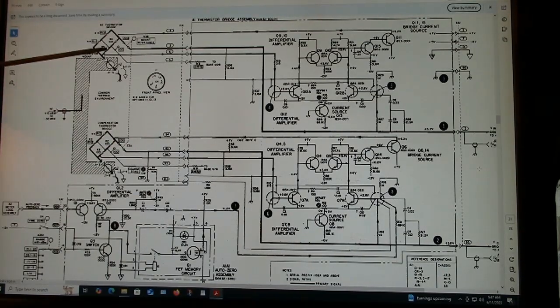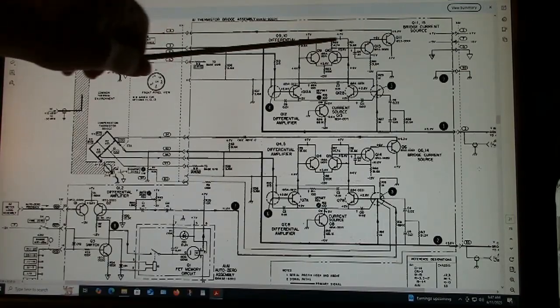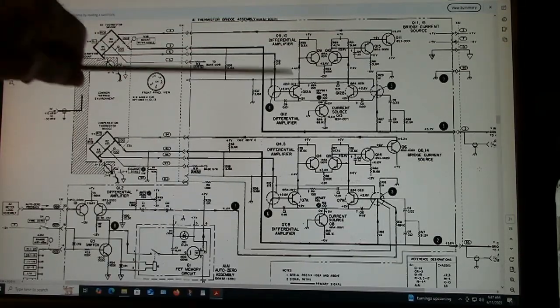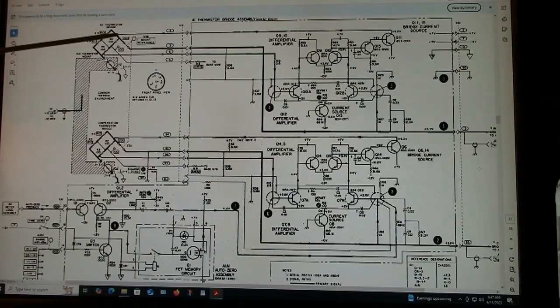Now when you apply RF, that will tend to unbalance the bridge, because this thermistor is heating up, its resistance will decrease. So to maintain the balance, this feedback system here, which is these differential amplifiers, will change the voltage at the top of the bridge to maintain that common resistance between the two. So then this voltage will actually change here. The reason they do that is it balances out any changes in ambient temperature, so that you're only going to measure the change due to the RF into this thermistor here.